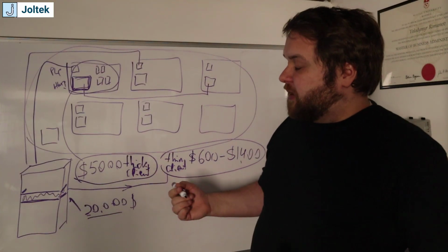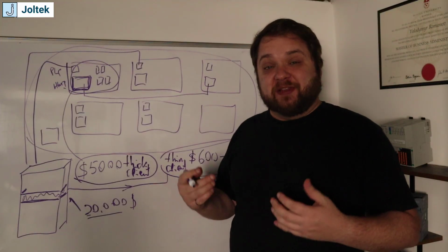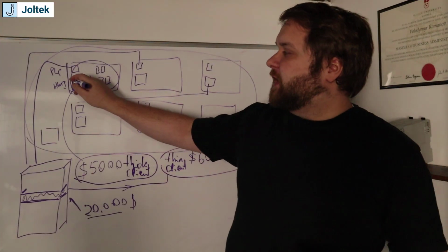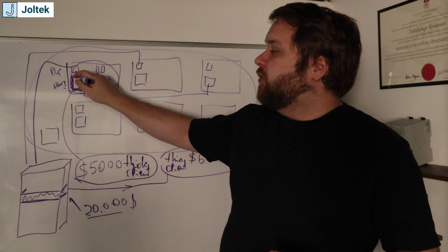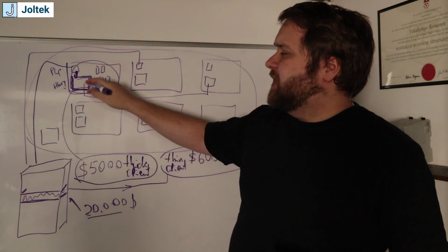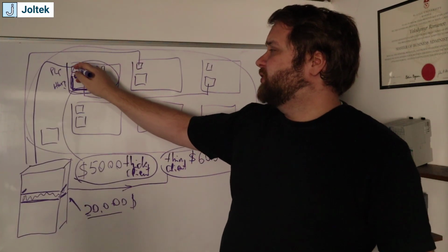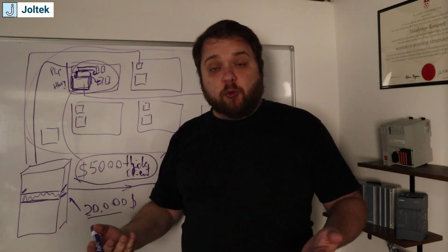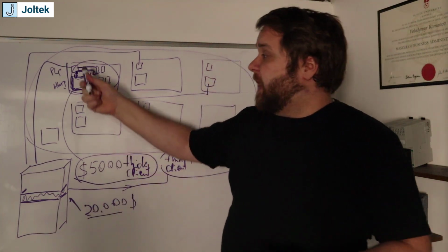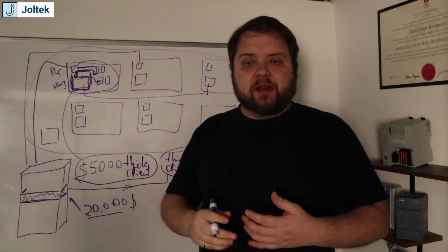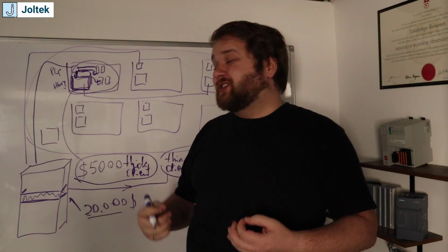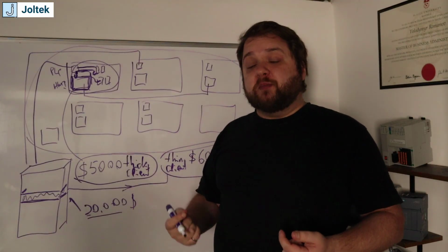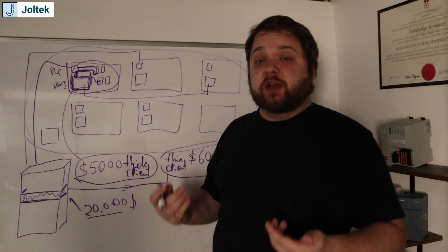And so in terms of data, right, I want to emphasize this because I believe many facilities miss this very important point. When you have a standalone HMI that basically only talks to the PLC, it's rare that the HMI is going to talk to your VFDs or servos. Usually that's going to be the job of the PLC, right? So the PLC, again, using a network switch, is going to get all of that data, and then that's going to display on the HMI. Well, that's all fine and good, but once you start scaling to this enterprise solution via a SCADA, the problem becomes more often than not your network architecture.